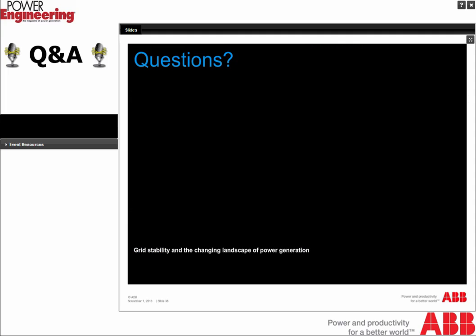Well, that's a great question, and I think the first one is really the stability-related issues. Do you need this rotating mass on the system to provide system stability? We've actually seen some parts of the country where you have a pretty high level of penetration of distributed renewable resources like rooftop solar. In one part of the country on the West Coast, you have that coupled with power plant retirements along the coast. And the distributed generation has essentially no inertia, no rotating mass, and that can lead to a rather significant challenge of having fault current contribution in the form of a synchronous condenser. So that's, first and foremost, in terms of a critical issue, that you're solving the fundamental needs of the system.